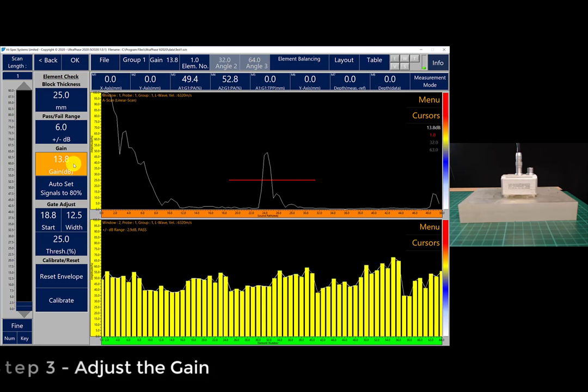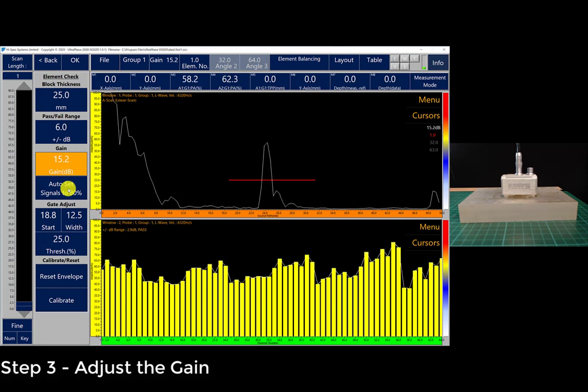Step three would be to adjust the gain so the maximum signal from the element envelope is at 80%. You are able to press auto set signals to 80% and you can see the signals across all the elements have been increased and the maximum signal on element number 55 is at 80%.